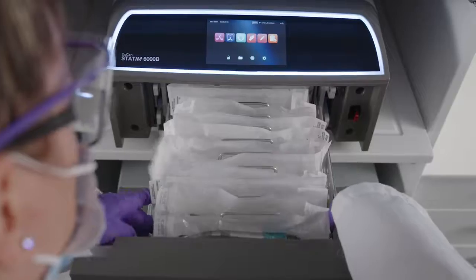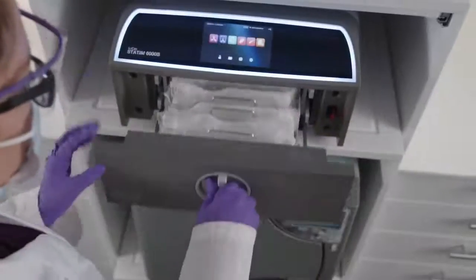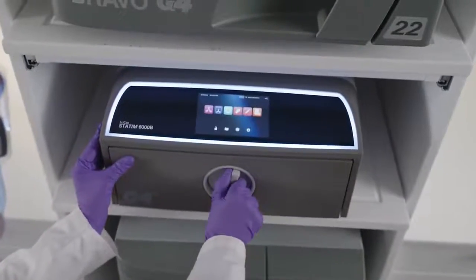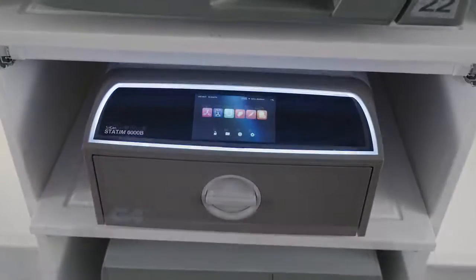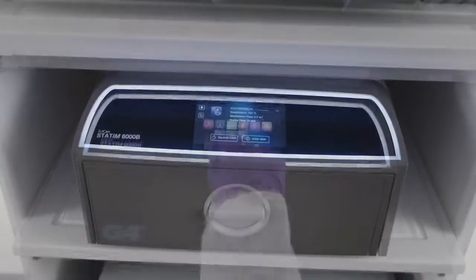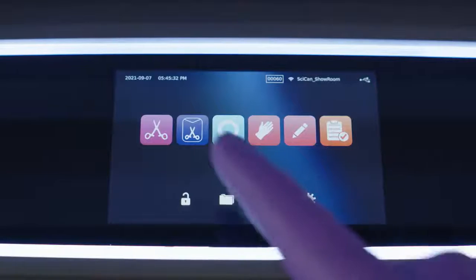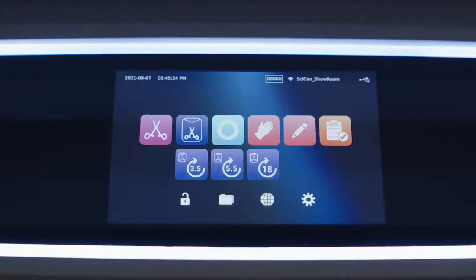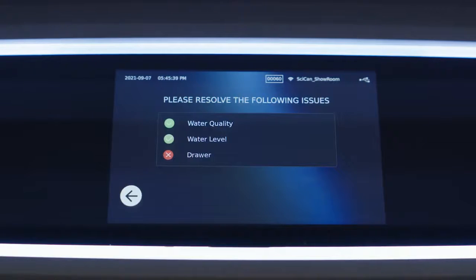Place the cassettes or pouches in the drawer and close and turn the knob to the locked position. Select the cycle appropriate for the load, then press the Start icon to begin the cycle. The STATIM B checks water quality, water level, and drawer status prior to starting a cycle. If there is an issue with any of these 3 conditions, the unit will not allow a cycle to start. Instead, a pre-cycle screen will appear to show you what condition needs to be addressed.